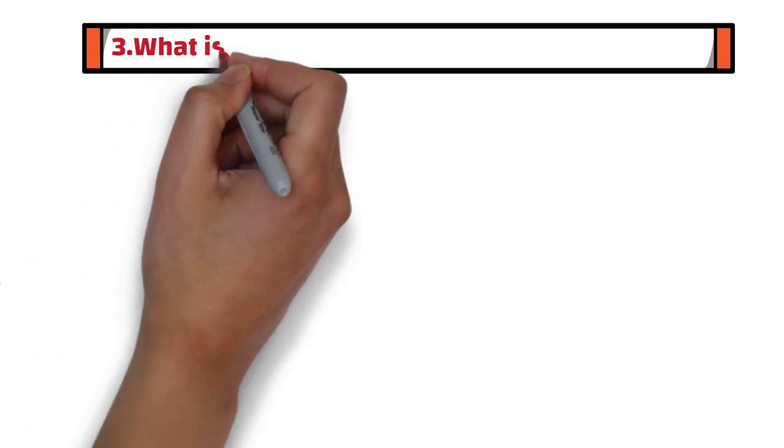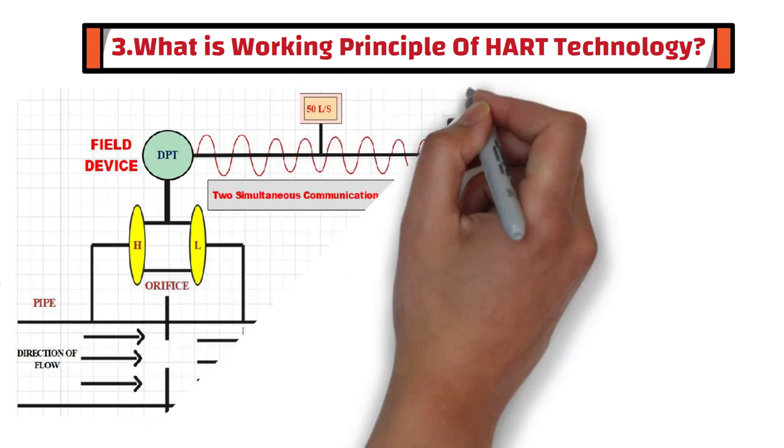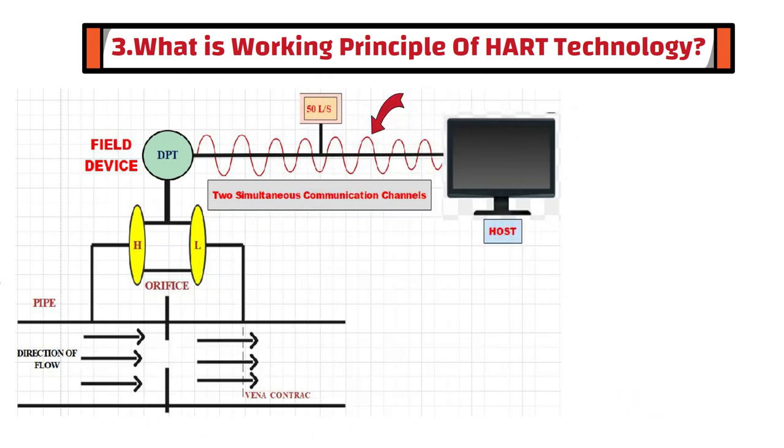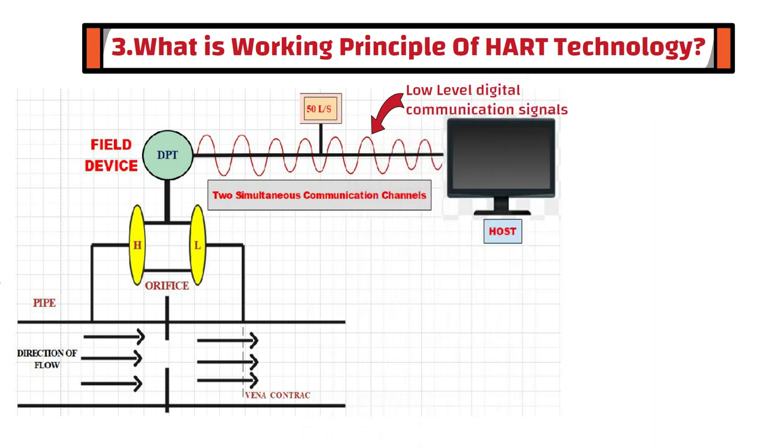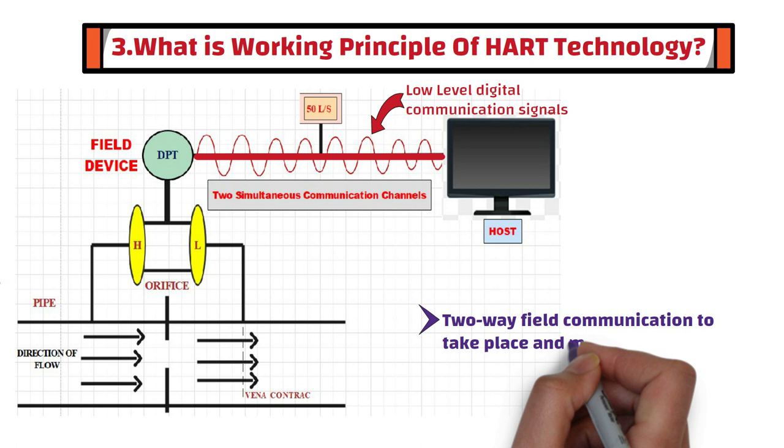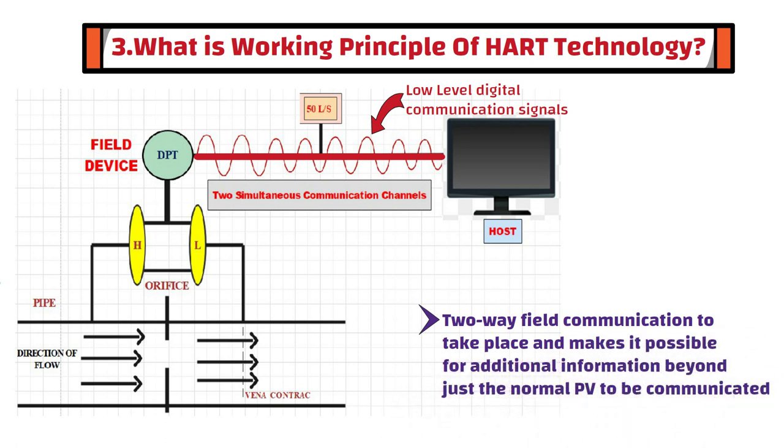Third question is, what is the working principle of HART technology? The HART communication protocol uses frequency shift keying standard to superimpose low-level digital communication signals on top of the 4-20 mA analog signal. This causes two-way field communication to take place and makes it possible for additional information beyond just the normal process variable to be communicated to and from intelligent field devices.